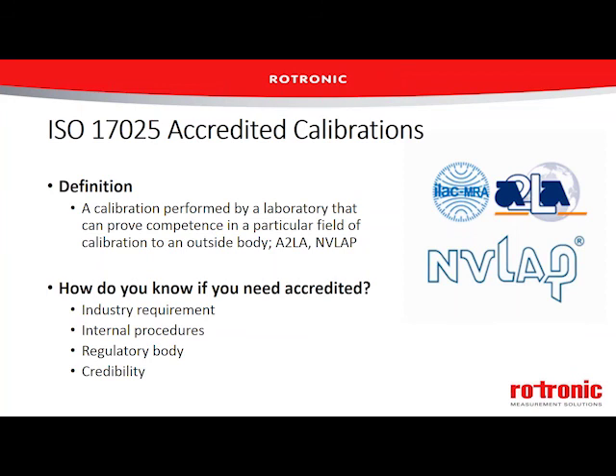So we might want accreditation. Perhaps your industry would require it, or your internal procedures require it. If you're an accredited lab, your internal procedures will most likely require that you use an accredited lab for all your calibrations, for all your reference equipment. Perhaps a regulatory body says, yes, we want to see accredited calibrations for everything, because when we've got the NVLAP symbol or the A2LA symbol on there, we know you've got proper traceability of measurements.